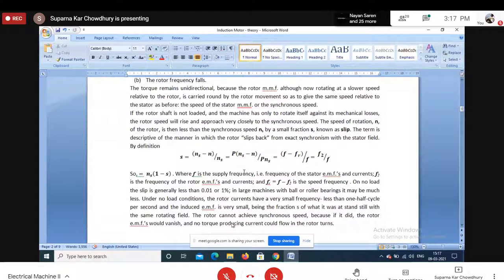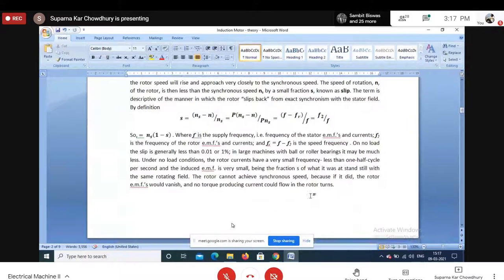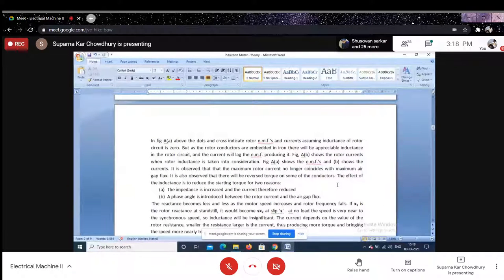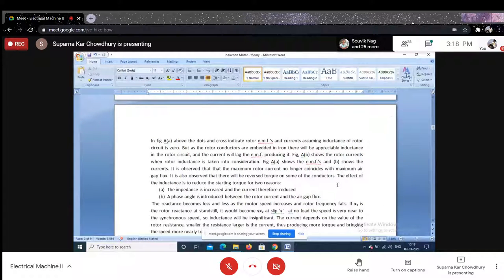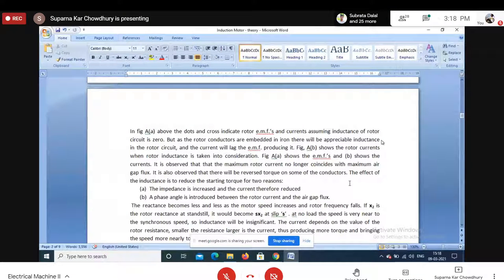As the machine is loaded, slip increases slightly. A well-designed induction machine normally has 4 to 5% slip (0.04 to 0.05). The secondary (rotor) frequency sf is therefore very low under normal running conditions. Because core loss is related to frequency, and the secondary frequency is low, we neglect the rotor core loss under running conditions.